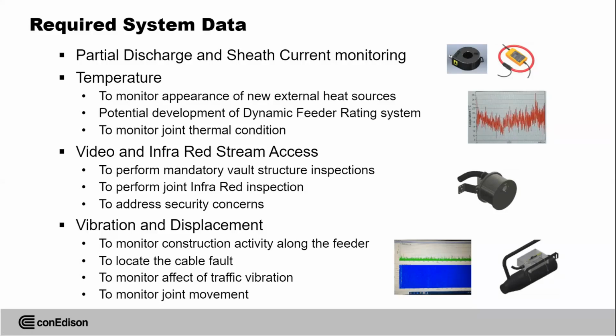Also, we plan to install vibration and displacement sensors. Vibration sensors are for a DAS system. It's a very well-known system for submarine cables and for military, right? So you can monitor vibration in the area. That can help us with routine patrol over our feeders, to see if anybody is using an air hammer, piling, or digging in the vicinity of the feeders. Signatures specifically for those operations can be put in the system, and you can see it and send your crew to verify what's going on in your system.